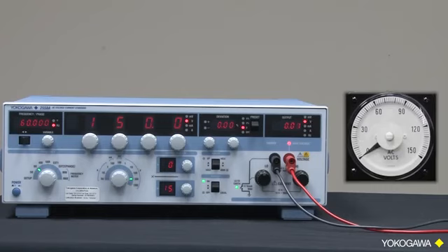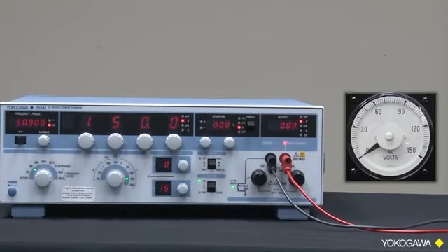To do this, set the voltage to a major division, then use the deviation control to center the meter indicator directly over the major mark. Now read the percent deviation on the source. It will tell you how far the meter is from its mark. Next, step the AC source to the next voltage level and repeat the deviation. To keep my demo simple, I will only show one example.